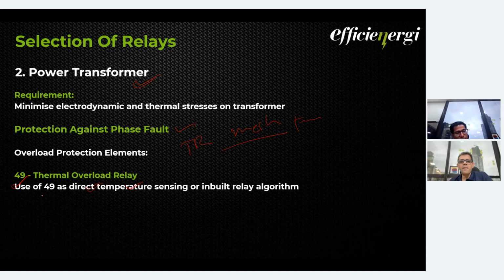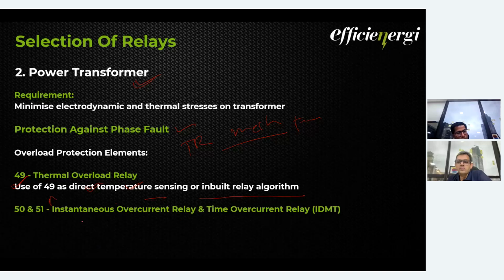Okay, so 49 has direct temperature sensing or an inbuilt relay algorithm. If the direct temperature sensors are there, then we can give the input to the 49 relay, or we can use the relay algorithm for thermal overload. While we are on 49, there's a question whether we can use it for HP motors also. 49 can be used in HP motors also. 49, right? Yeah, definitely. 49 you have to use everywhere.